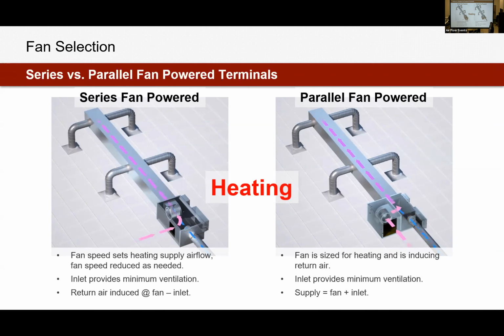If we switch over to heating, now we're going to start bringing in some of that warm plenum air. In your series box, our fan is still running because the fan always has to run in the series box. The only difference is that we're changing the air through the primary valve. We're in heating mode, bringing our fresh air or our cooling down to a minimum. We're down at that minimum ventilation, so we've got a small amount of air pulling through here. The fan is inducing the rest of the air through this return, which is usually open through our plenum.